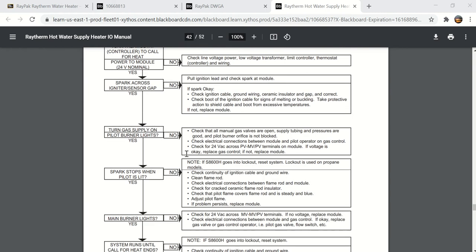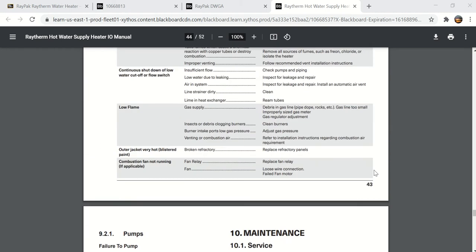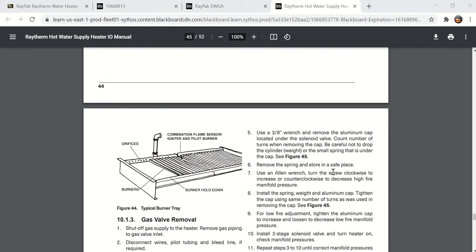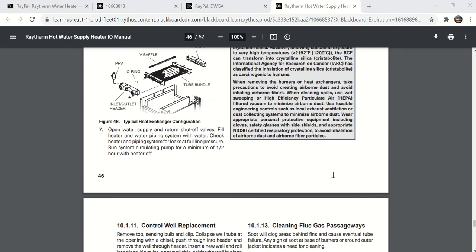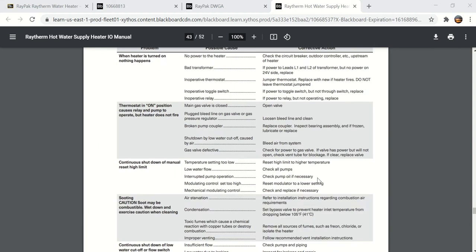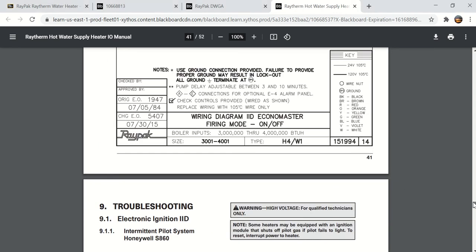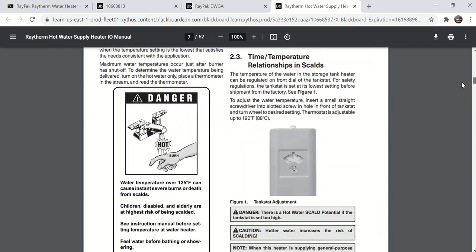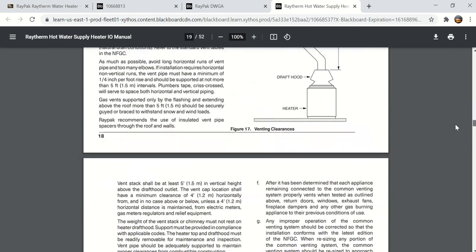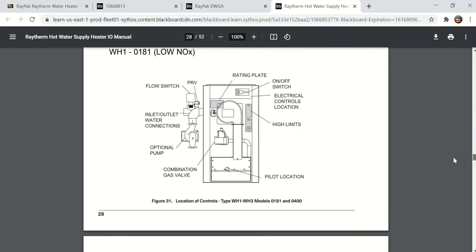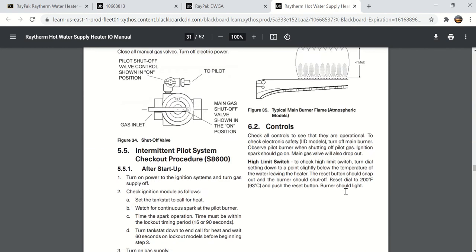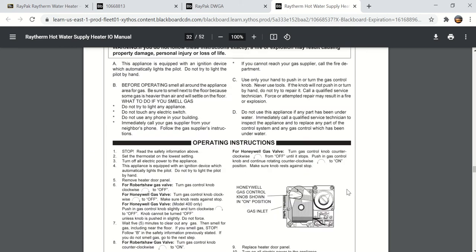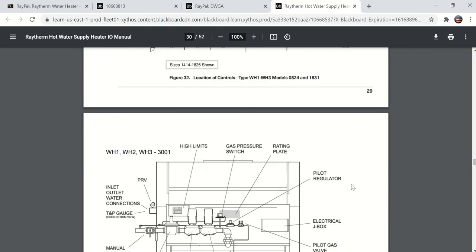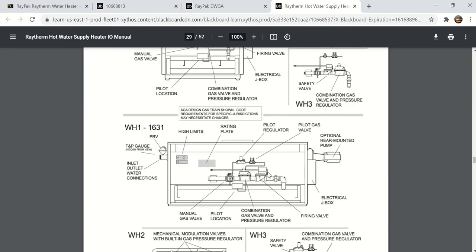So here's some troubleshooting information. So I'm going to use some of the things in this manual to put on the quiz. So take a look at some of the things here. There's a couple different wiring diagrams, but I will try and focus on the function of the solid-state economaster device, which was the main purpose of this. It's a time delay relay, and the fact that this is an atmospheric type burner. Here you see the dual gas valves, the pilot gas valve there. Here's the pump. Here's the flow switch.